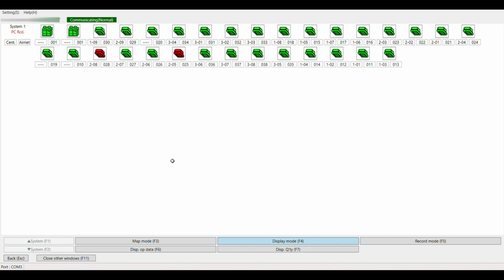We did get some red icons though, which means there's an error code on the equipment. Basically what happened, the end user decided they did not want controllers on some of the indoor units, and by removing the wiring from them, the units went into alarm because then the indoor unit couldn't communicate with the nav controller. It was an easy addressing fix to make them all work in one group, but I took this screenshot before we did anything to show you what it would look like because this is a somewhat common error. You'll also get this error if you duplicate any addresses on the network, another reason to have that as-built with you that we talked about in part one of this project.